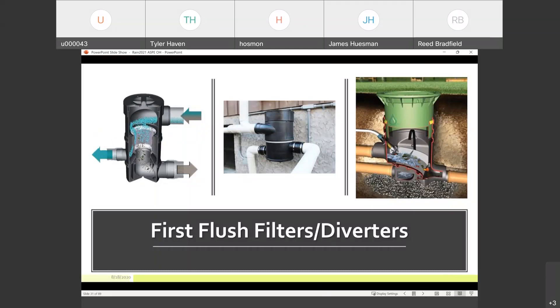We find that these vortex filters have their place. Another lesson learned: be careful when you put these things inside a building — make sure there are floor drains and they're not anywhere where the potential for flooding could occur. We've had instances where they were plumbed up incorrectly, didn't have a long enough run into the unit itself, and they got back pressure blowing the lids off of them. Check with the manufacturer or vendor on installation. We'd like to see them outside the building, not inside.